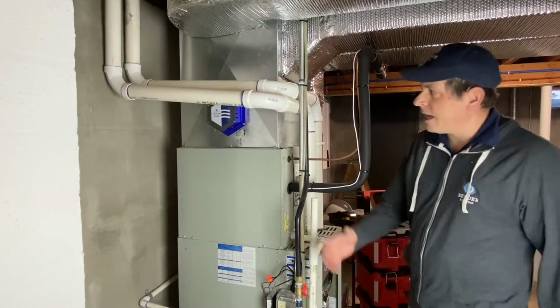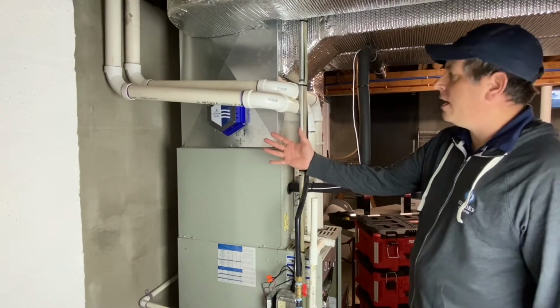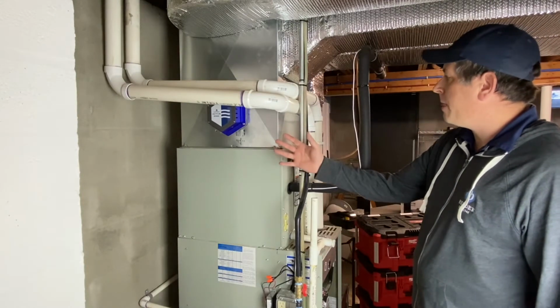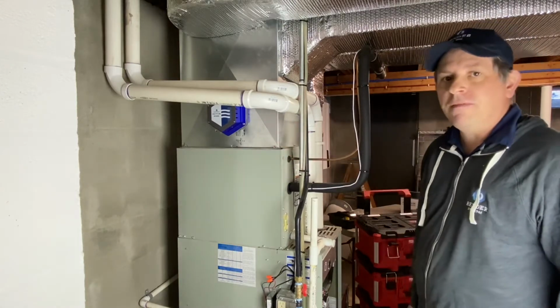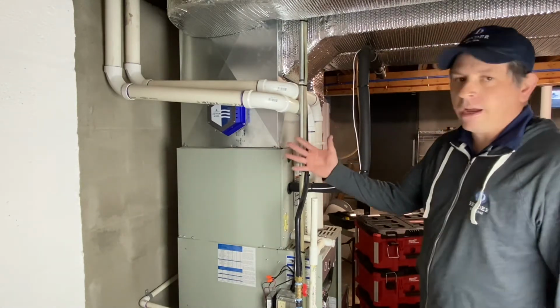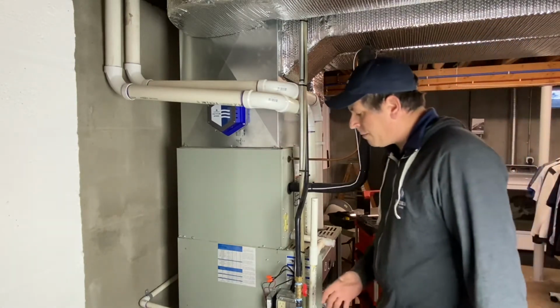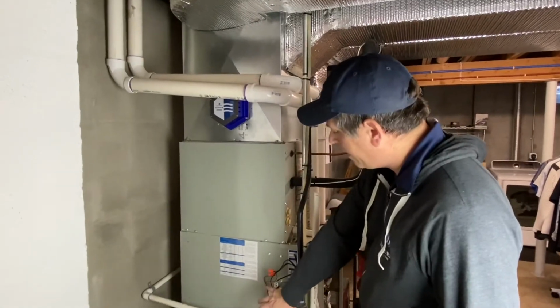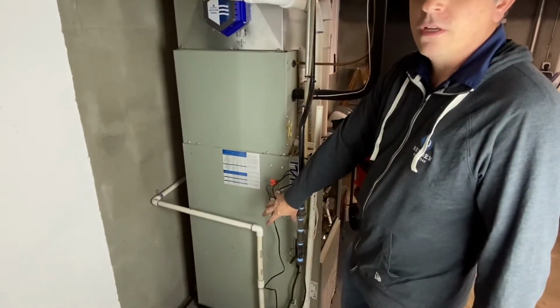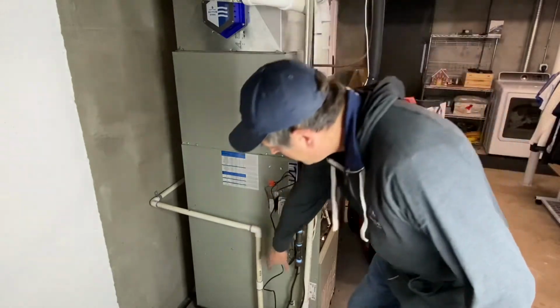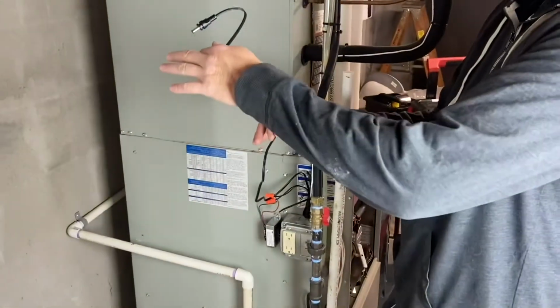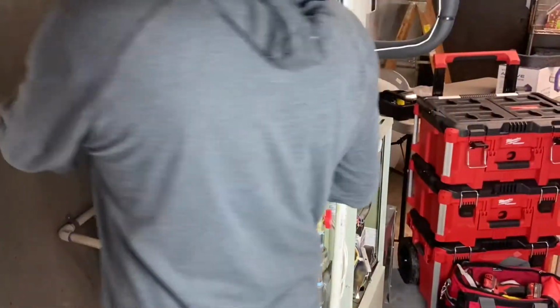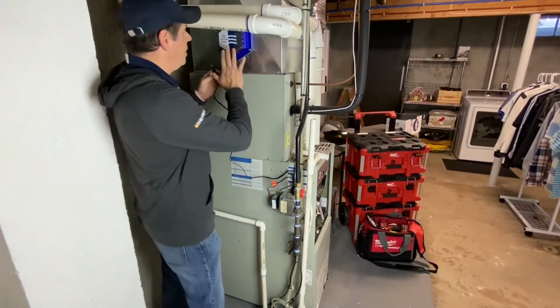Now that we have our Dust Free Active mounted on the plenum, on the supply plenum above the evaporator coil, we can now wire it. We prepared this by putting a transformer down here that steps it down from 120 volts to 24 volts, which goes to our plug, and it's going to come over here onto the other side of the active.